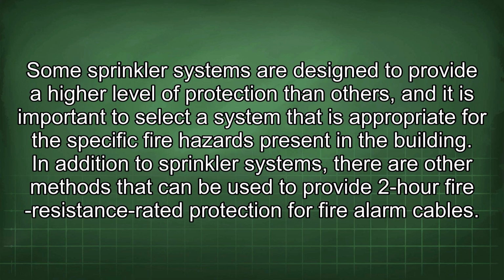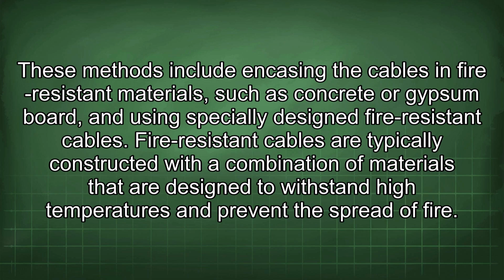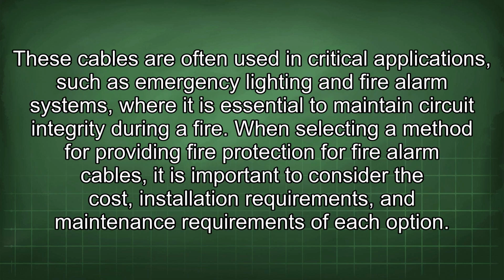In addition to sprinkler systems, there are other methods that can be used to provide 2-hour fire resistance rated protection for fire alarm cables. These methods include encasing the cables in fire-resistant materials such as concrete or gypsum board, and using specially designed fire-resistant cables. Fire-resistant cables are typically constructed with a combination of materials that are designed to withstand high temperatures and prevent the spread of fire. These cables are often used in critical applications such as emergency lighting and fire alarm systems, where it is essential to maintain circuit integrity during a fire.